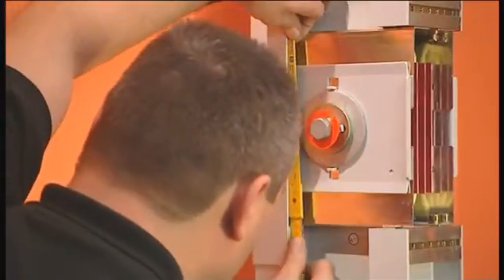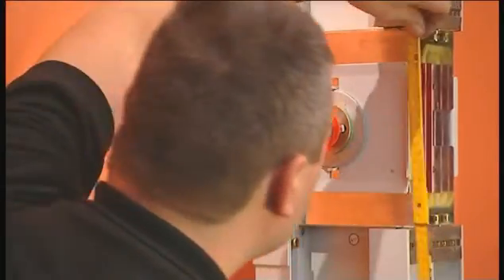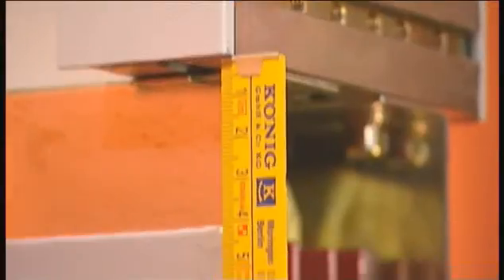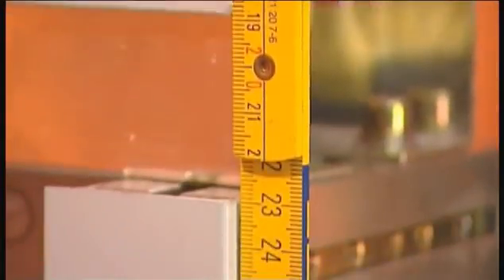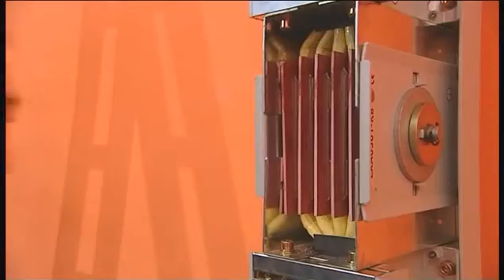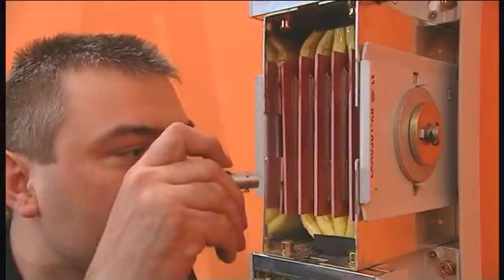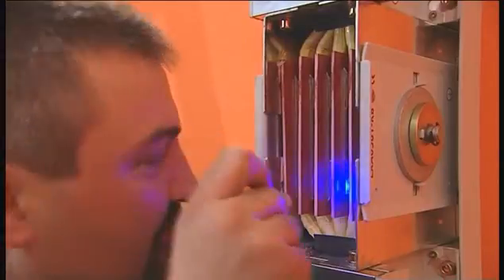The distance between the two trunking units must be checked. It must be 230 millimeters. A visual check ensures the clamping block is properly mounted. The clamp is in the correct position if the mark is centered.